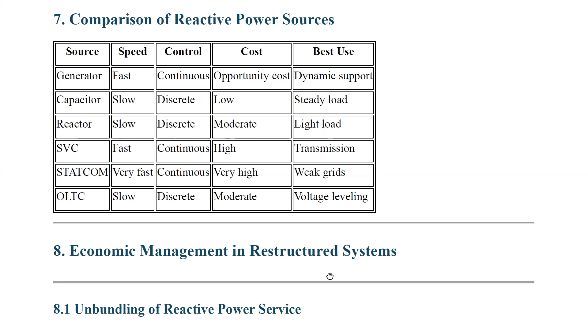Next, reactors. Speed is slow, control is discrete, cost is moderate, and they are best used for light load. But this kind of light load happens only a few times. Based on that, our generation itself will decrease based on the feedback. Next, the static VAR compensator: speed is fast, control is continuous, cost is high, and usage is for transmission lines. Next come the STATCOMs: speed is very fast, control is continuous, cost is very high, usage is for weak grids. Next comes the OLTC, on-load tap changing transformers: speed is slow, control is discrete, cost is moderate, and usage is for voltage leveling.